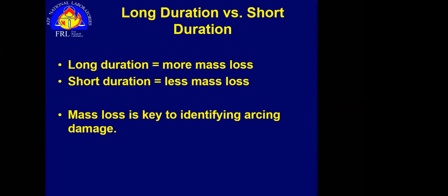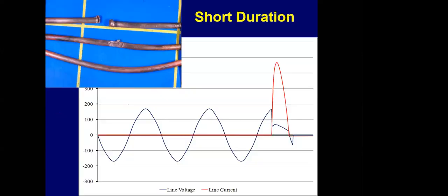Furthermore, 921 talks about an arc as being the actual discharge, and a spark as a particle that's glowing, either because it's so hot that it's glowing, meaning it's probably around 1,000 degrees Fahrenheit or higher, or it has combustion occurring on its surface. I like to keep things simple. A spark is, if I arc two wires together, the particles that fly away, the mass loss. Or I can have sparks from welding or grinding or cutting. The ignition handbook refers to those as mechanical sparks because it's a physical particle. So I think I beat that enough.